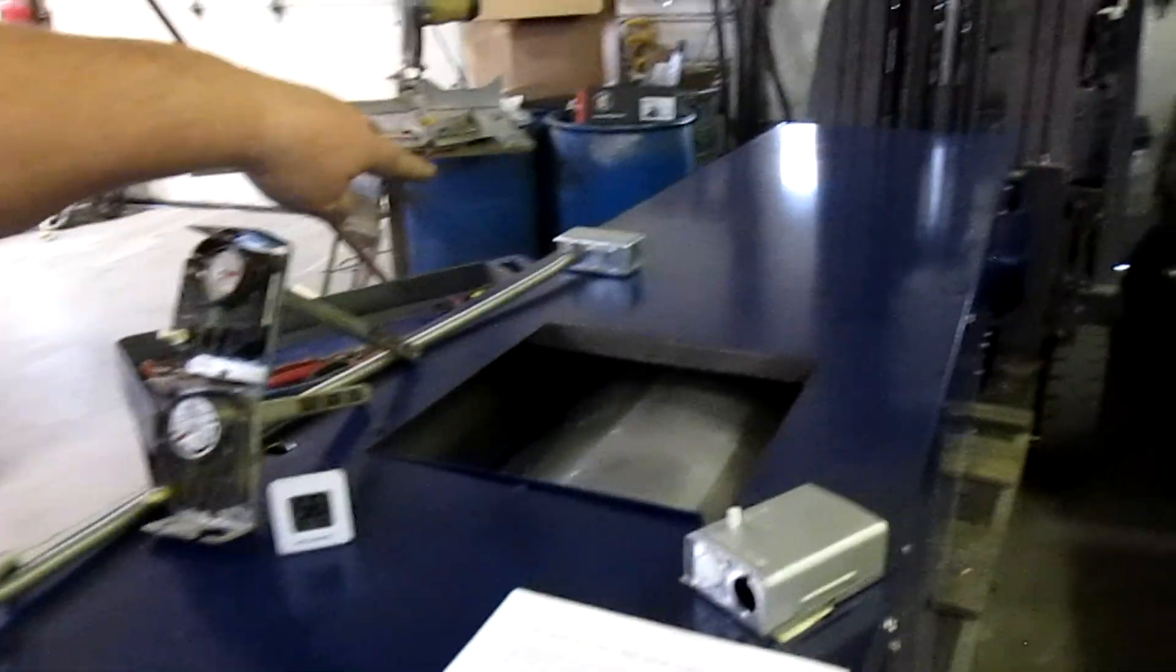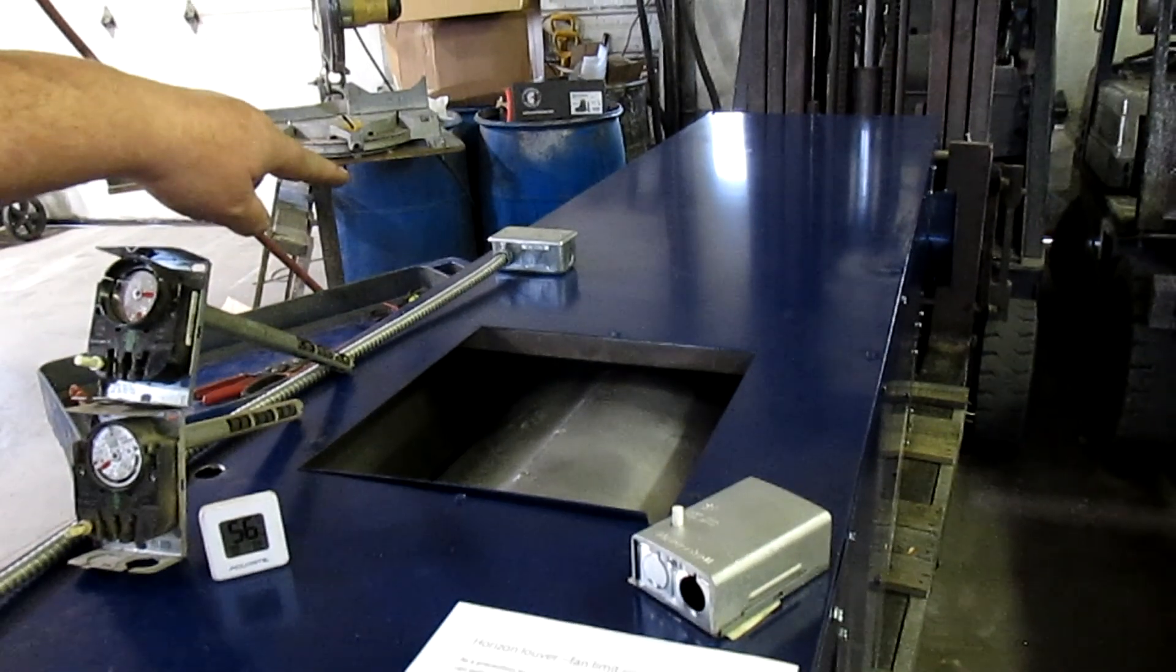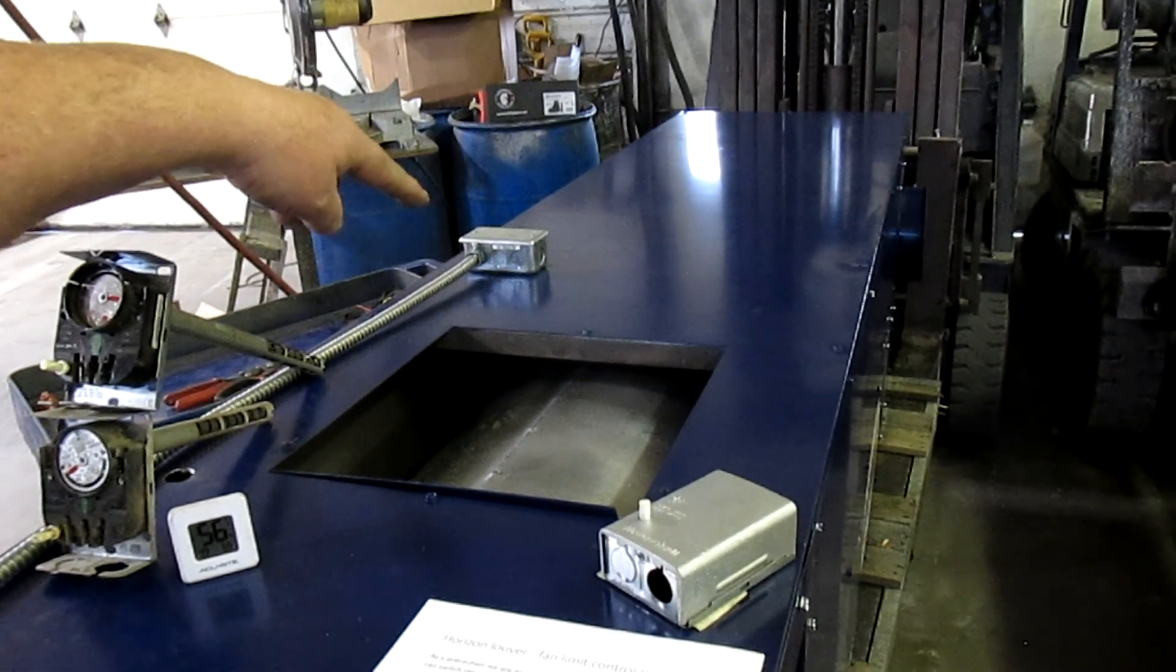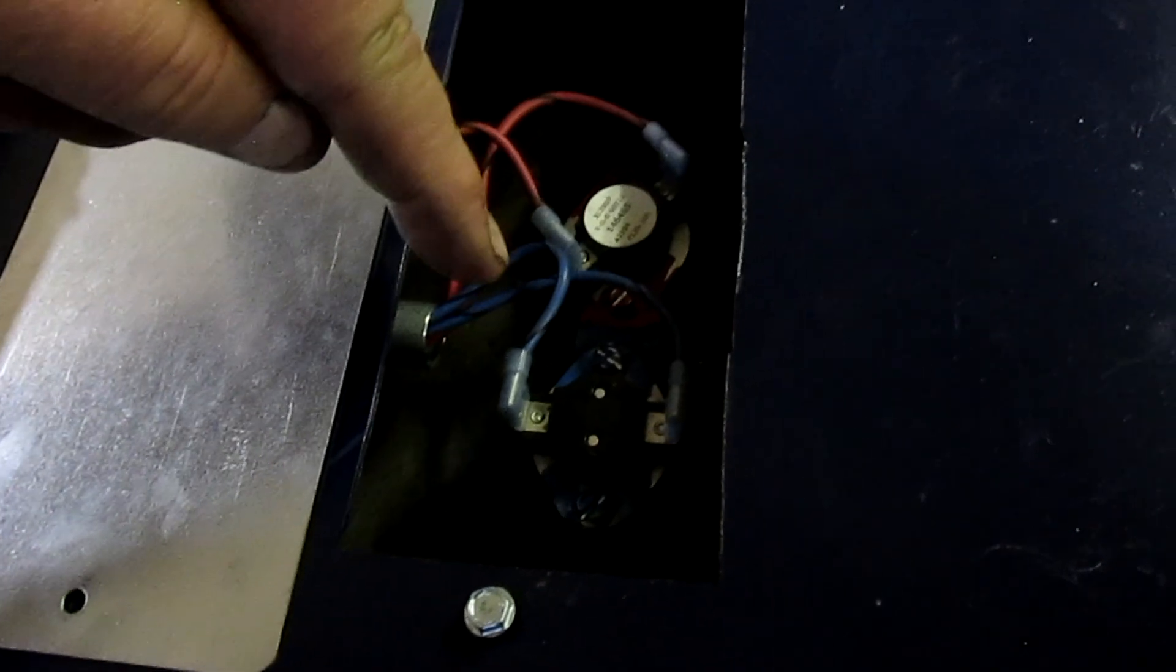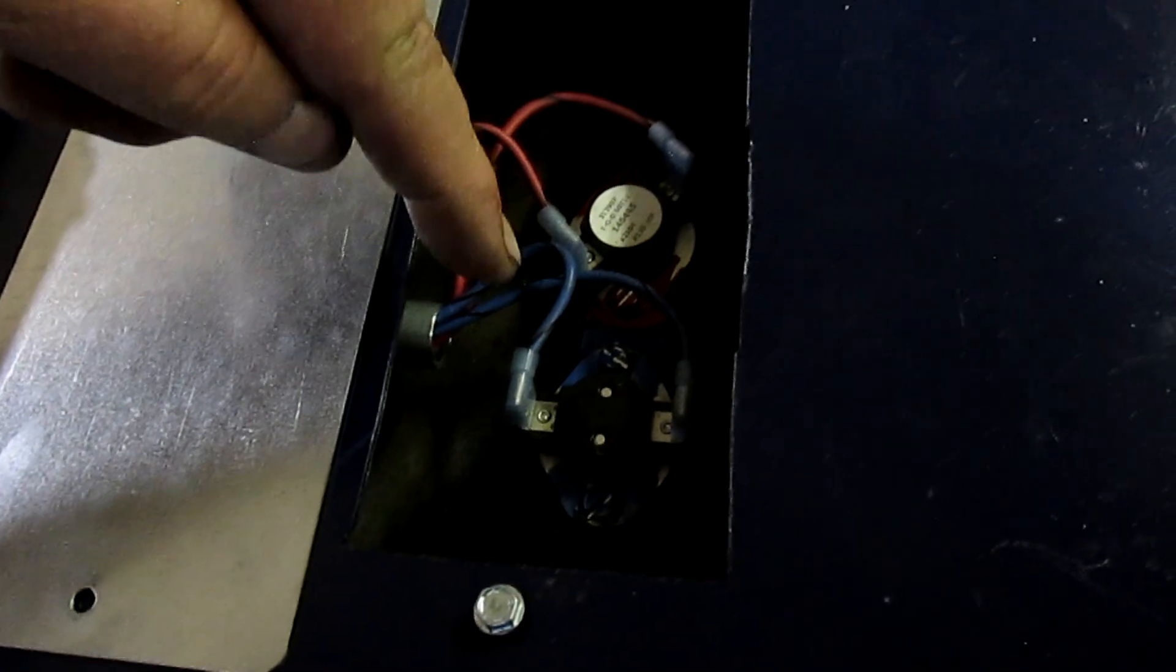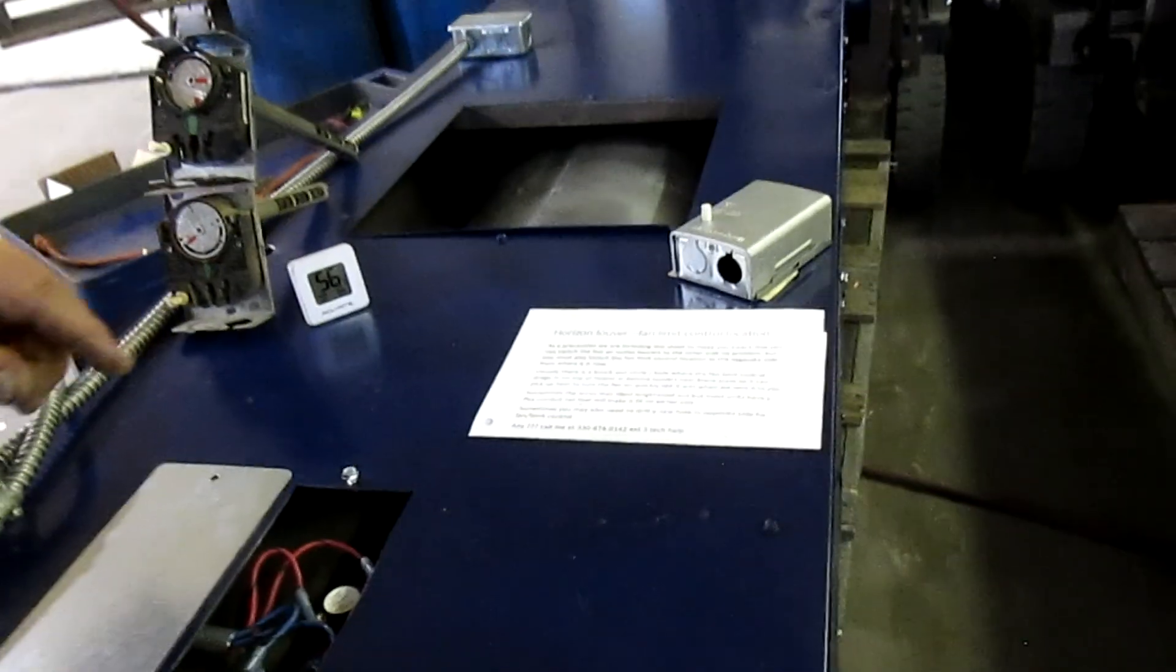It has a fan failure switch. If the fan never starts, that's the hottest spot of the unit right there. It'll shut it down in the event of a fan failure. This here switch will shut it down in the event of high air temperature, and the original fan limit switch will do the same.